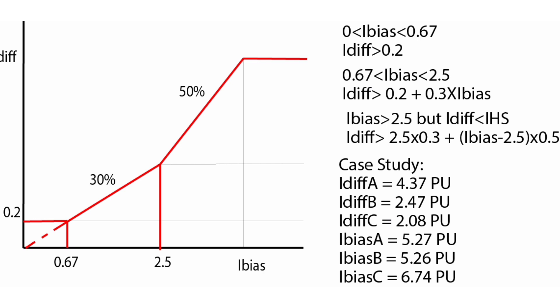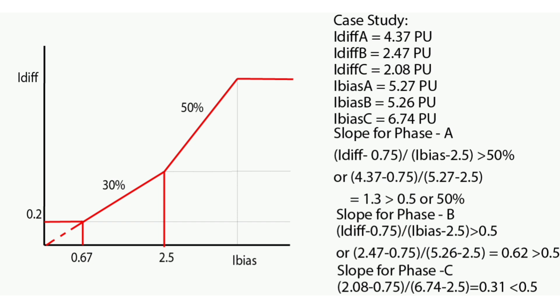For phase A, since the bias currents for phase A, phase B, and phase C are 5.27, 5.26, and 6.74 per unit, we can conclude from the characteristics curve that the bias current falls in the 50% slope region. So the differential current must be greater than 0.75 plus (I_bias minus 2.5) times 0.5 for the relay to remain in the tripping region.